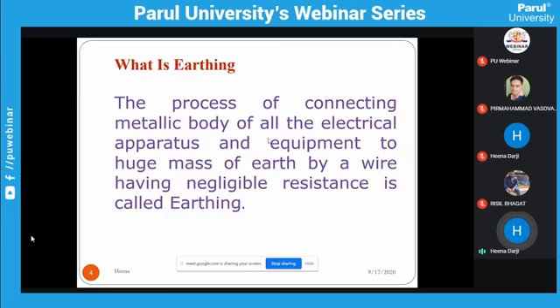Now, what is earthing? The process of connecting the metallic body of all electrical apparatus and equipment to the huge mass of earth by a wire having negligible resistance is called earthing. Apparatus means our iron and all that, and equipment means big equipment in a substation, like CT, PT, current transformer, potential transformer. So grounding and earthing are the same, but in some places people call it grounding and some people call it earthing. Grounding is the word used in the USA, and in Britain and England people use the word earthing, and we are using sometimes grounding and sometimes earthing. Both are the same process.